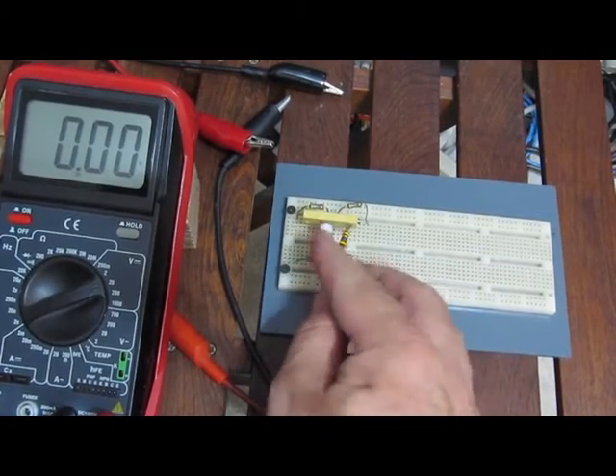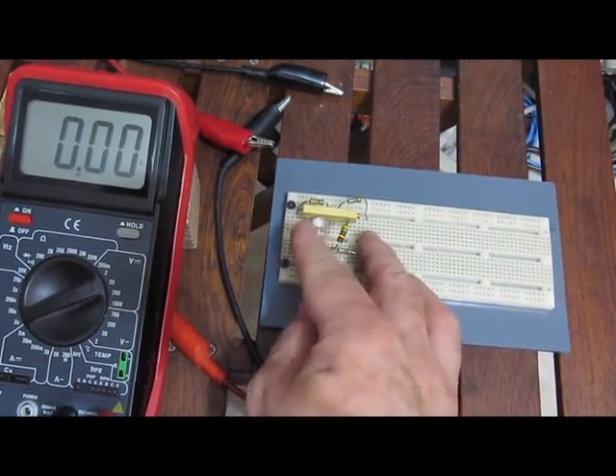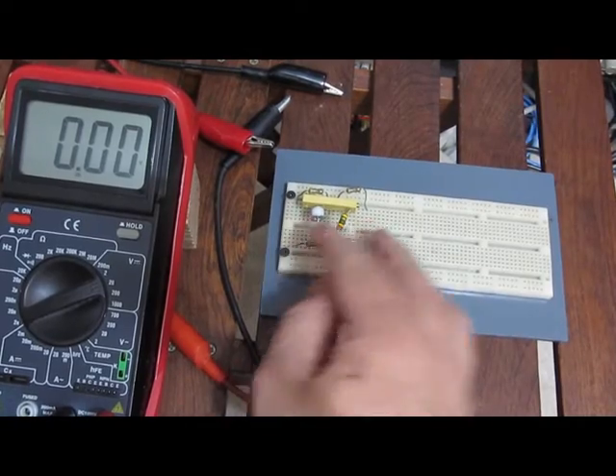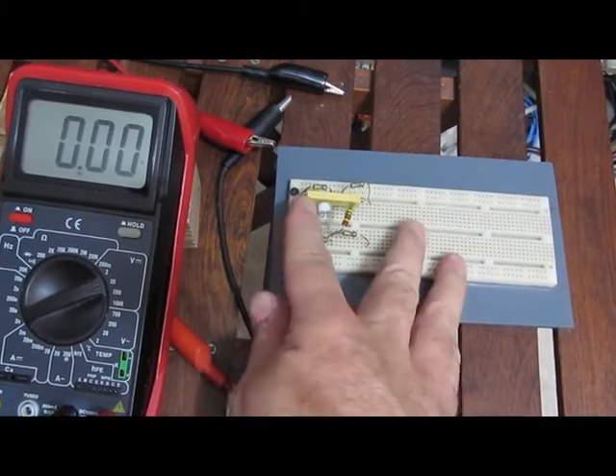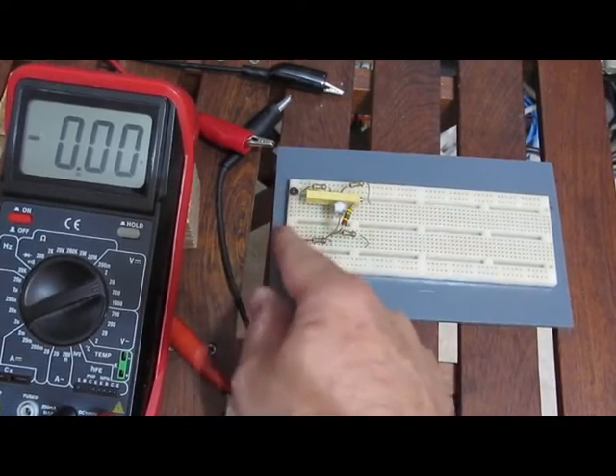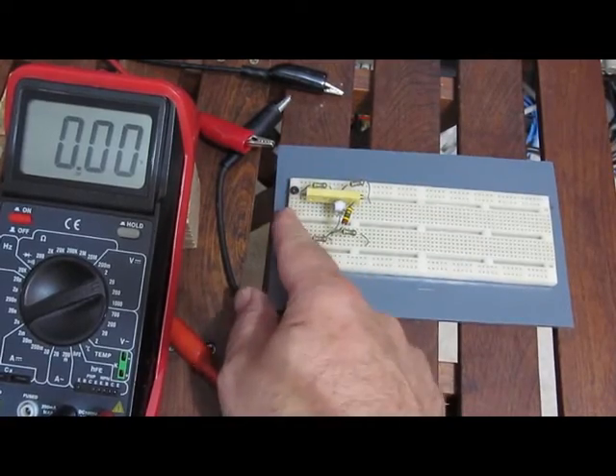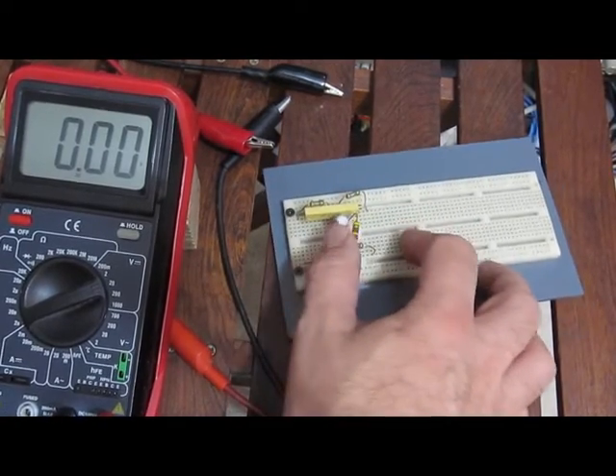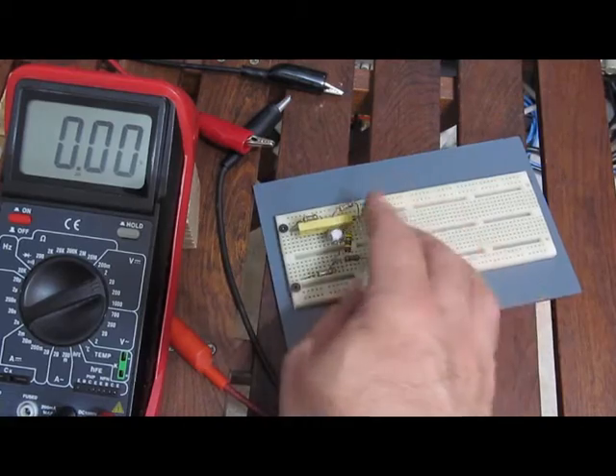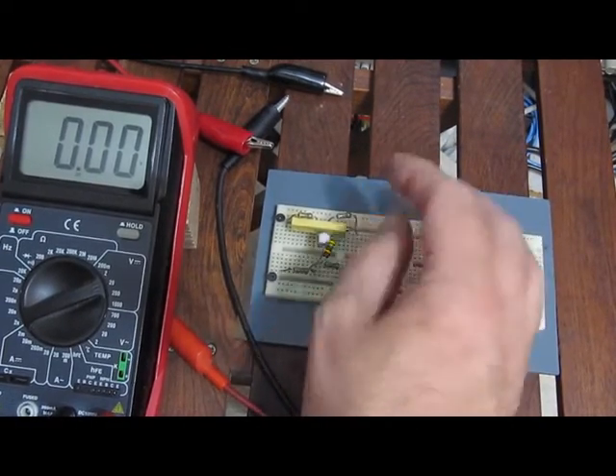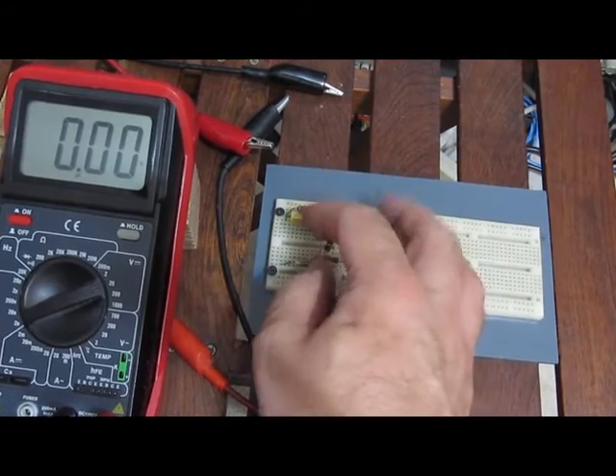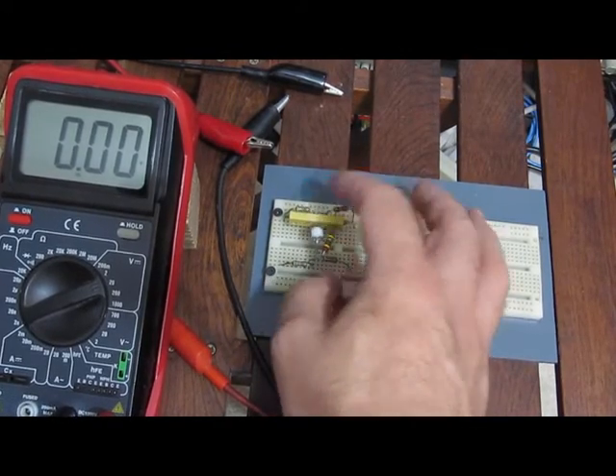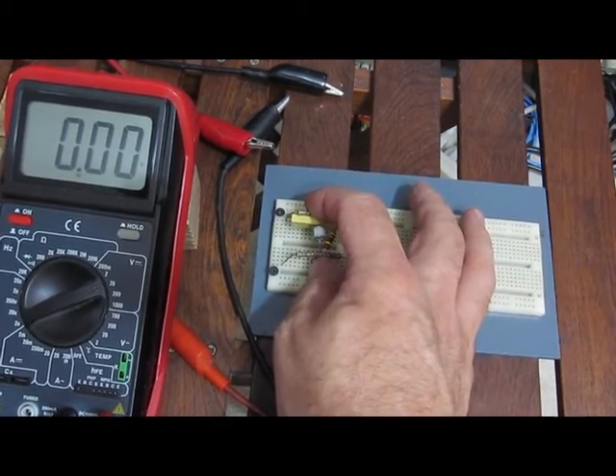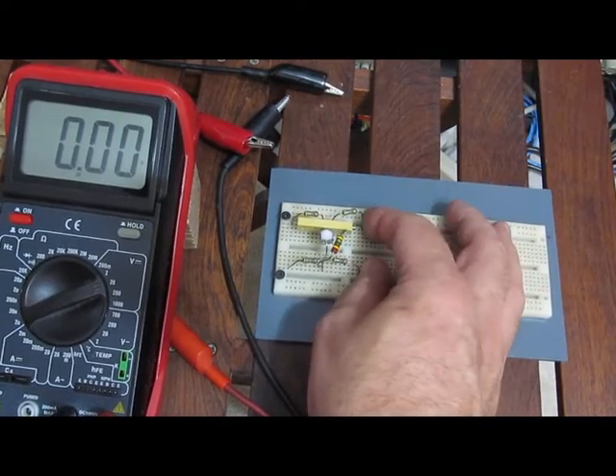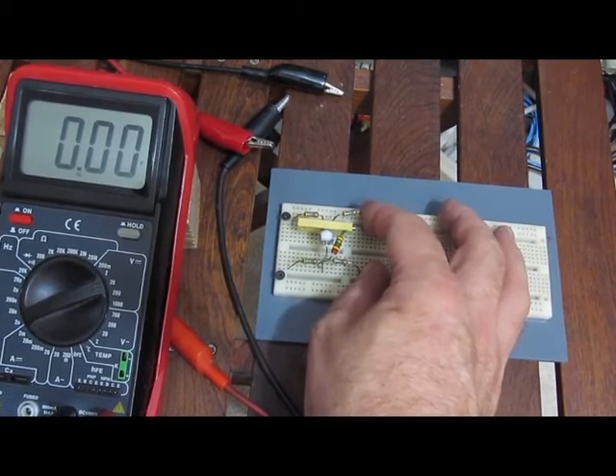One thing in this prototype I want to show you is this GDT, a gas discharge tube. The reason I'm showing that is if a transient were to come in - say I was measuring 1,000 volts and we got a 10,000 volt spike - we don't want to pass that spike down to our meter. So this gas discharge tube will fire and short this out at the center here, and the voltage to the meter will essentially fall to 0 volts.